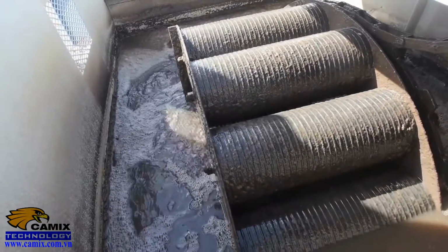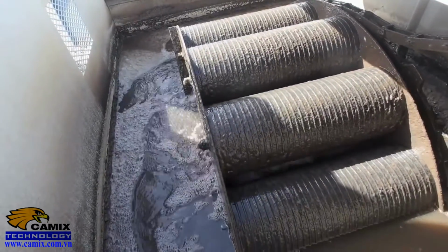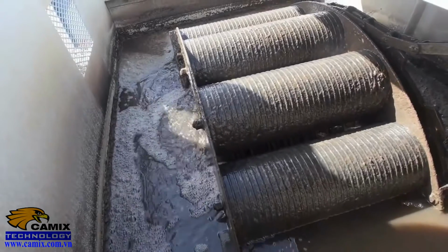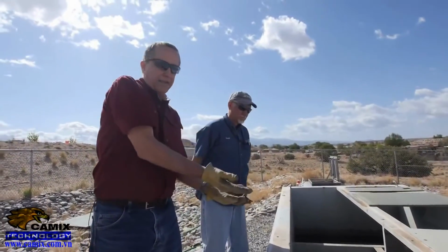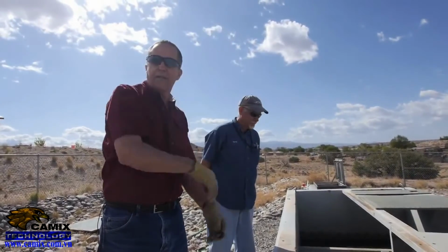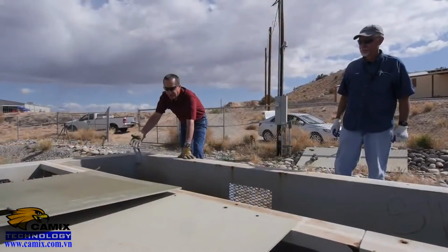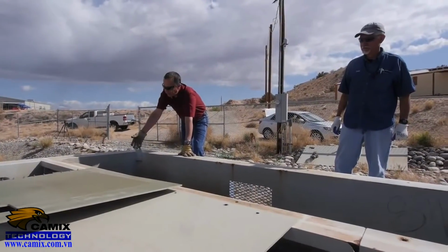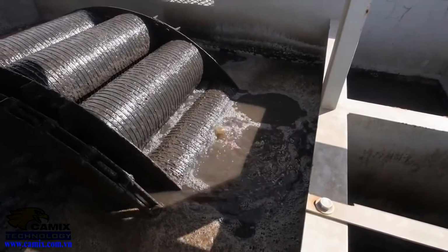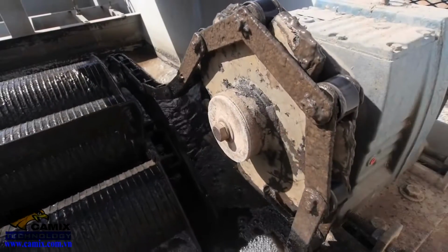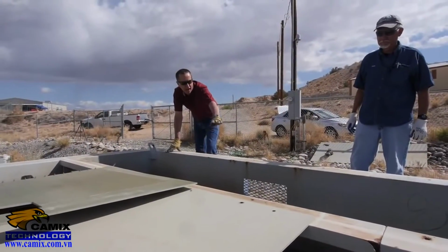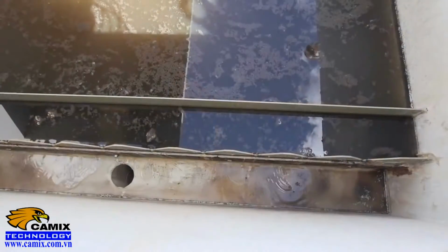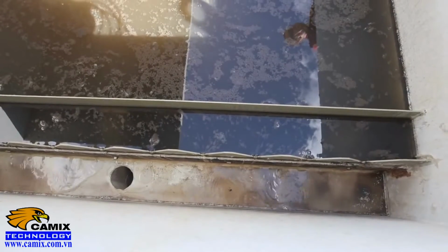And then when the drums empty, they're full of air, they're full of oxygen, and then they submerge again on this end. They take that oxygen back down to the bottom of the tank and they slowly bubble that oxygen up through the mixed liquor. We've got the clarified primary sewage coming into the head end of the plant here. The level of the aeration basin is slowly rising, and eventually the level will equalize and we'll start seeing clear effluent spilling over the weirs down at the other end.